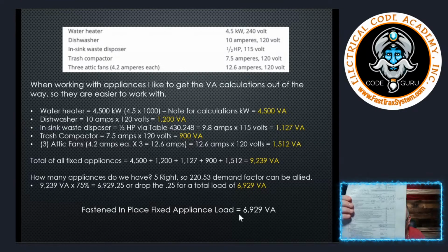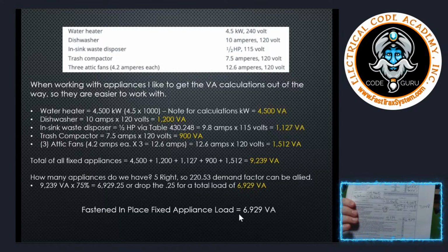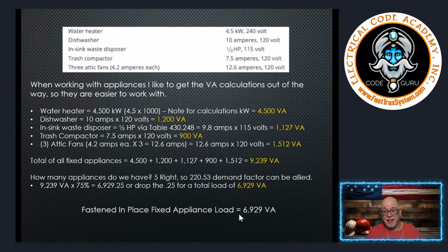Now, you might say, let's move on to the dryer. But remember, what we're doing while we're going down this list, we're working on that neutral at the same time. I love to work at the same time. So when you look at these loads here, notice something. There is only one of them here that utilizes no neutral. That is the water heater. Water heaters do not use a neutral. Okay, it's just a heating element. All right, doesn't have a neutral element to this.